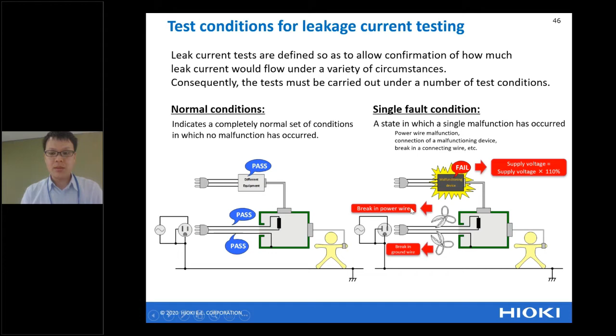Okay, so next, the types of leakage current testing. From the standard, we can say there are six kinds of leakage current testing. Today, I want to explain three typical measurements for leakage current testing. The first one is earth leakage current. The test objects are class 1 equipment and class 2 equipment with functional earth. We also need to check if the earth is broken. So in that case, also, to keep safety, the leakage current must be small like this.